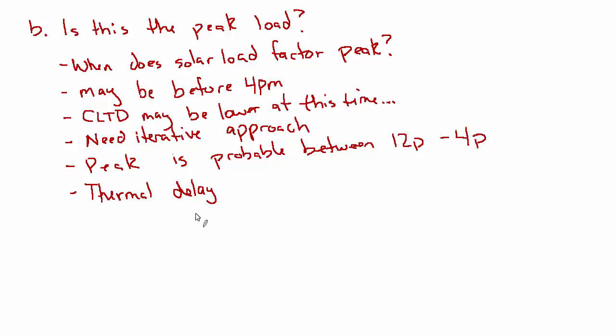And it really depends on the building materials and the situation as to how big of a factor this thermal delay is. But just speaking from my own experience managing a commercial office building in New York City, operationally we had situations where you would expect to see the peak load at 1 or 2 o'clock. Everyone's coming back for lunch. It's a hot summer day. The air conditioning is cranking. You have the maximum number of people in the building. The doors are being opened many, many times so there's lots of losses on paper. You would expect that to be the hardest part of the day to get through. And yet, for whatever combination of reasons, the peak cooling load when the chillers would have to work the hardest and when we would start to bump into capacity issues potentially when the building's fully occupied was really later in the day between 3 and 4 p.m. And this was a consistent thing. It's not like one particular day where the sun was behind the cloud at 1 p.m. and it was hotter or the building was being exposed to more sun later in the day. This was a consistent pattern that we observed throughout the hottest days in July.